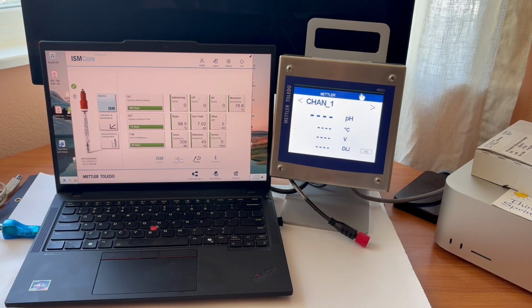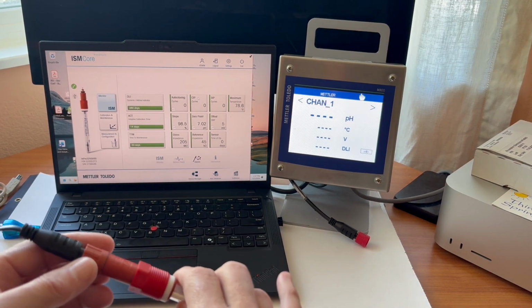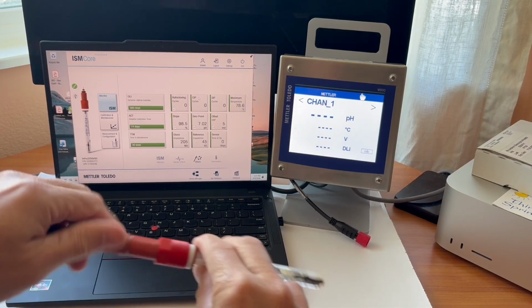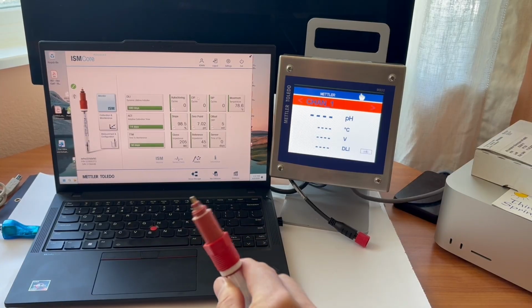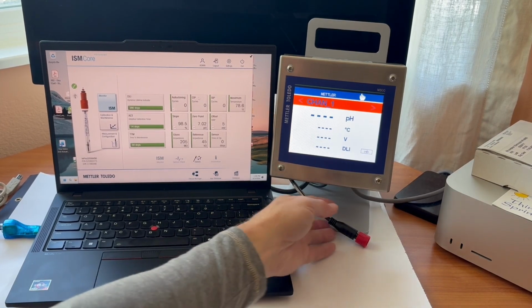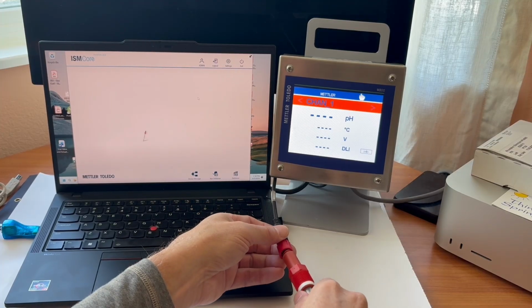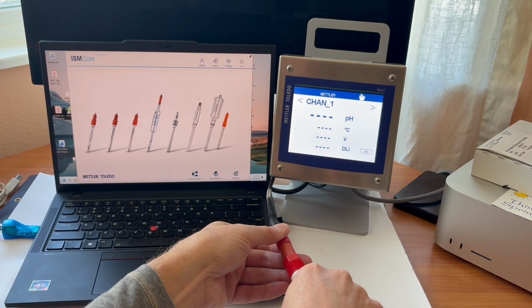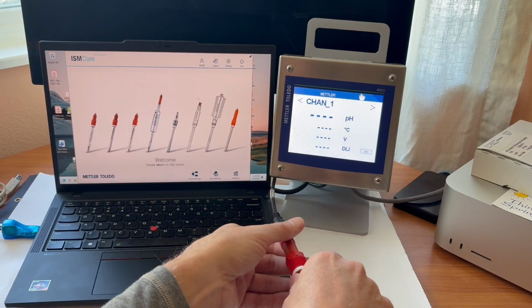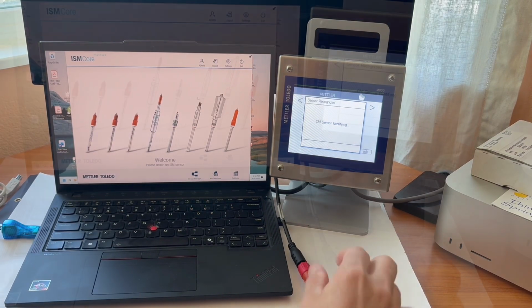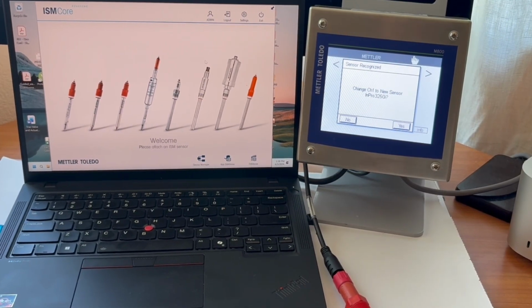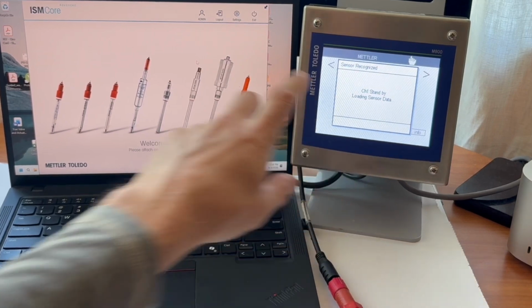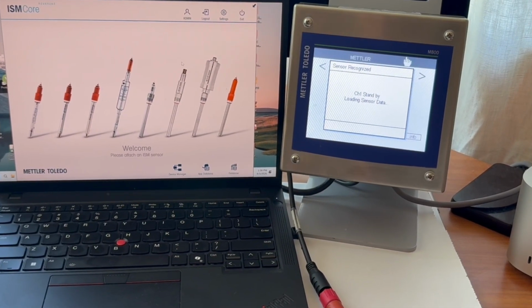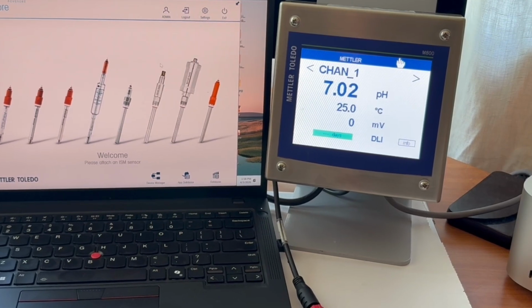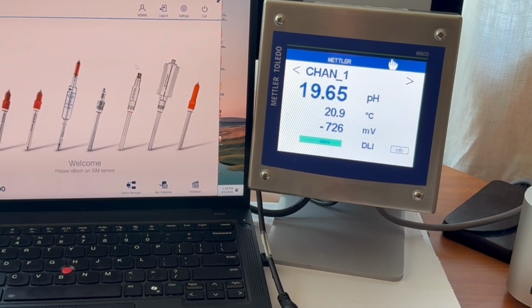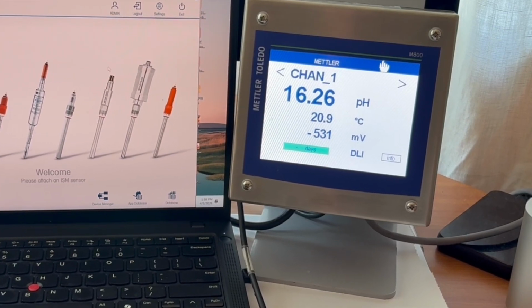So here's an example with that sensor still connected to the software we just calibrated in the shop. We will disconnect it and connect it directly to our transmitter. Say we jump on our truck, on our bike, whatever, go out to the loop. We'd uninstall the initial sensor that's out there. We'd pull it out. We'd swap the sensor. This is now saying, hey, you have another sensor on here. We accept it. It does that electronic handshake. It will actually then load the calibration data and everything associated with that sensor and go right into measurement mode.